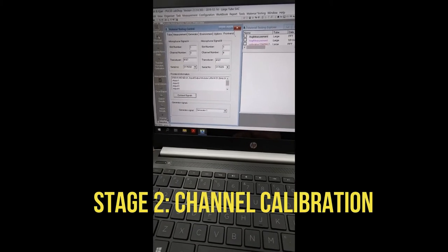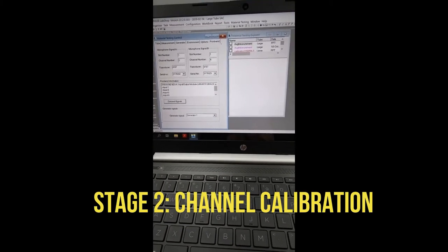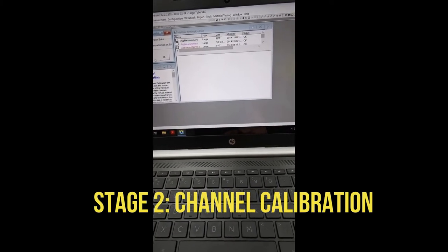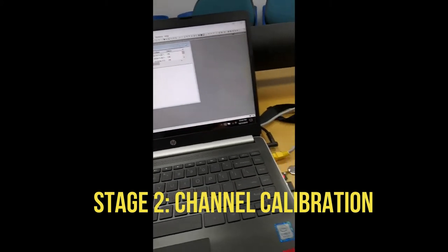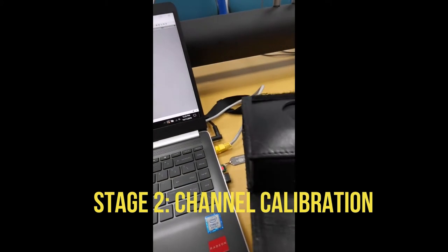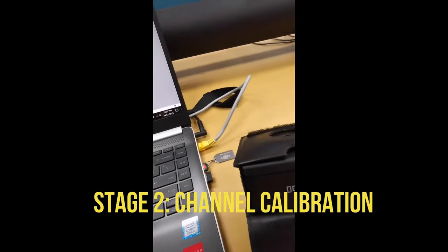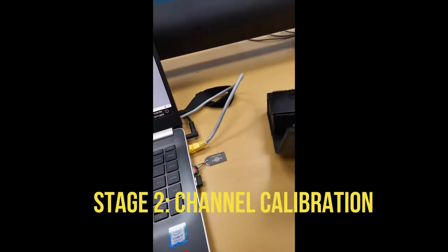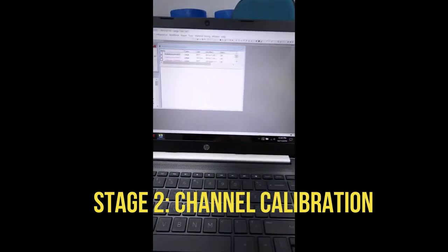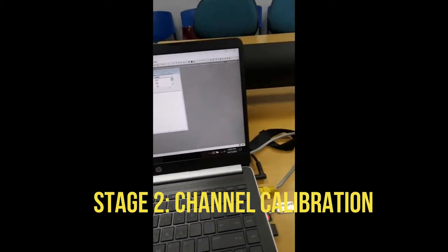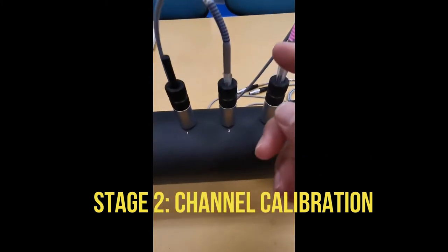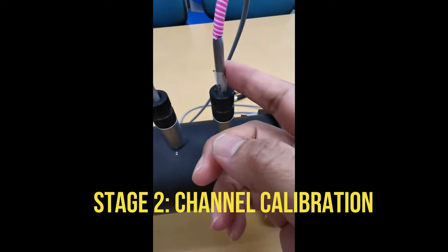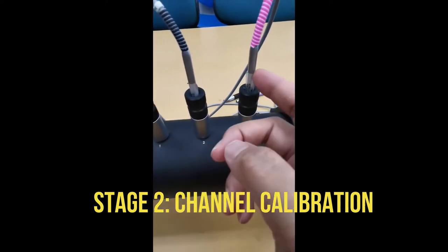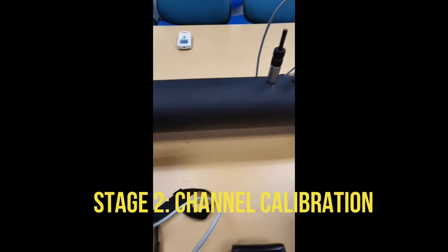The next step is channel calibration. Press channel calibration. This is the calibrator, and we will calibrate the microphone. This is microphone A and microphone B, and we're going to calibrate both of them.